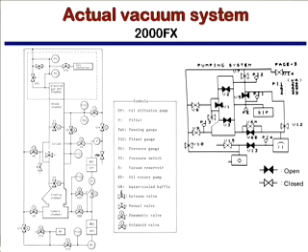Again, on the older system we have downstairs, I just checked, it's actually 21 years old at the moment, okay? So we're finding that the goniometer is getting a little leaky, so sometimes we have problems there. So when you put the sample in, what you first do is you pump with the roughing pump on the sample region so that you don't introduce air straight in, right? And then when that gets good, you go ahead and put a little bit of air, the 10 to the minus 3 volume in, and it pumps away from there, okay? I think that's the way the 2000 FX works.